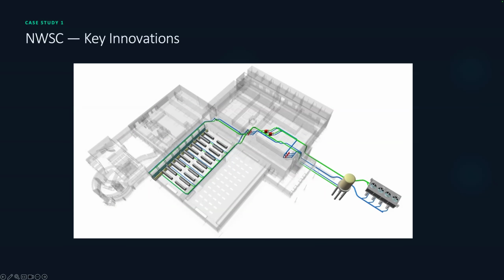So this is a ghosted image of the whole facility. It gives you kind of a whole picture. And one of the things about efficiency is we were able to strip down to just the absolute bare minimum components. If you really think about the system, from the data center to the heat exchanger, there's three sets of pumps and two heat exchangers. So the internal water that's cooling the data center is completely clean, never sees outside conditions. We put corrosion inhibitors and the normal kinds of water treatment you would in a closed loop building. You got those multiple headers, and you can reach to any computer system on the floor that requires liquid cooling. And so you're just circulating fluid through that loop, supply and return.